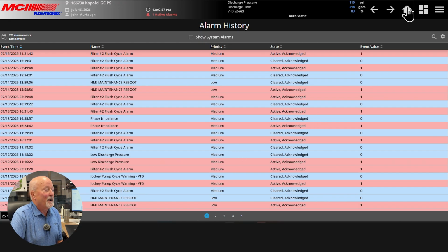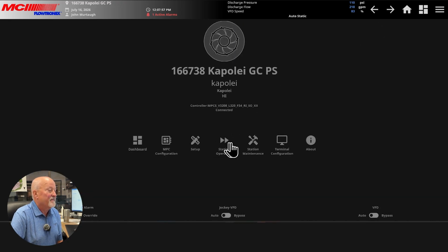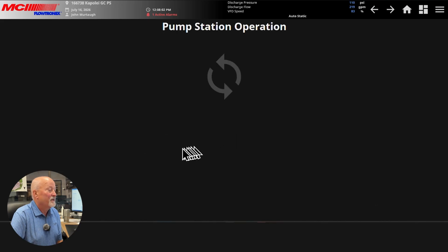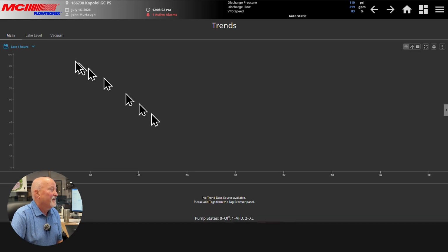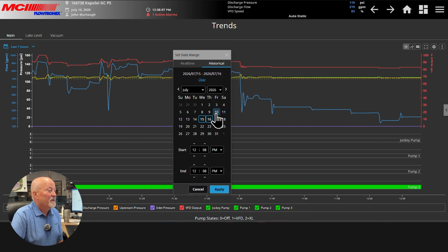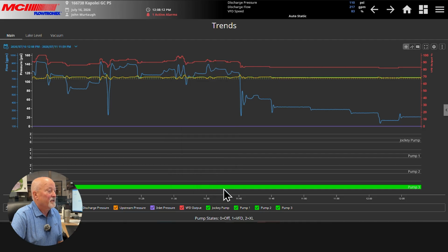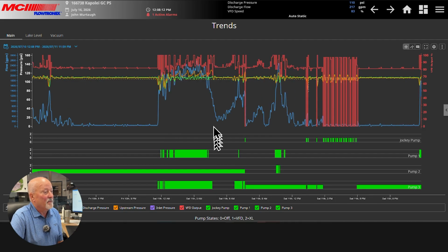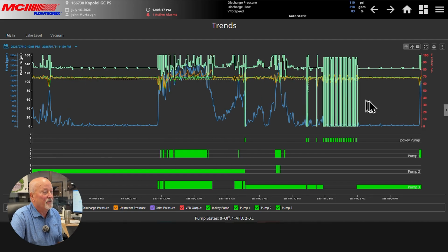So now we're going to go back and we're going to get on the graph. So we'll go to station operation. We're going to go to our graph. We're going to click up here. We're going to go to historical and say, let's look at 710 to 711. It's going to pull it up. It's going to take a minute. It loads the whole thing, and you don't have to hunt very much to see here's where the problem was.